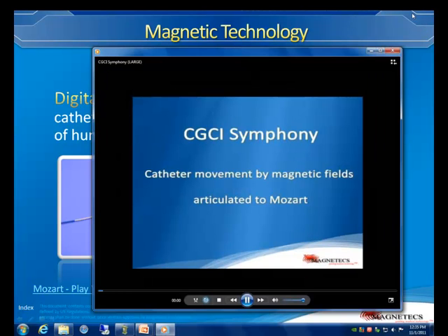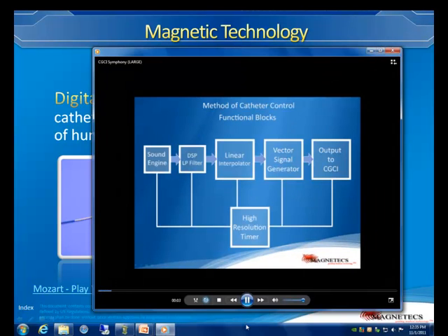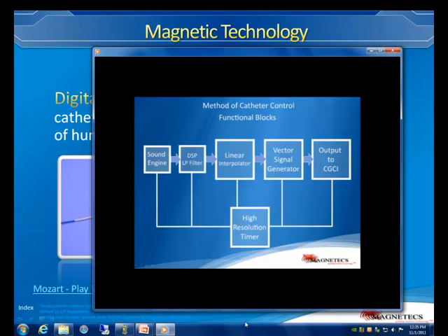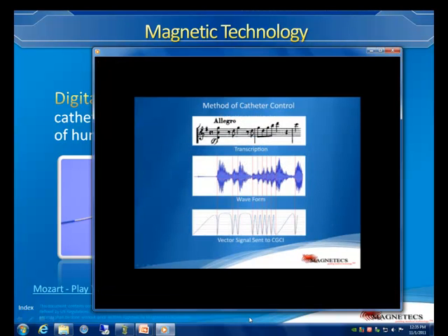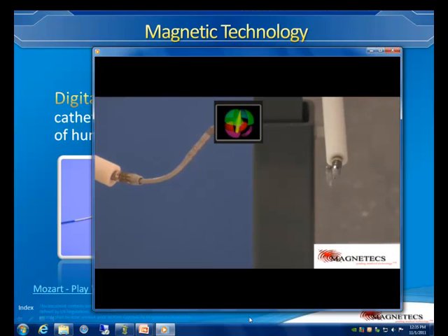So you can see the agility of moving a magnetic field. Remember, we're talking about a massive amount of energy, and they're switching at around 200 milliseconds. The reason for that is all our coils have a very, very low inductance.